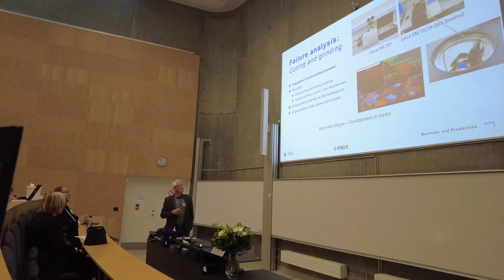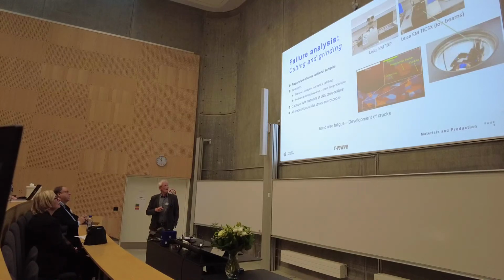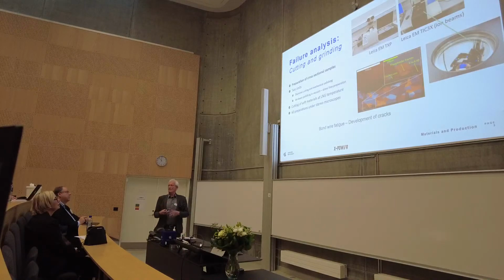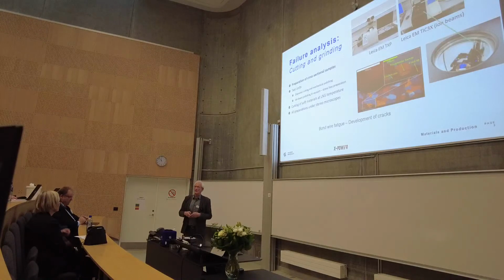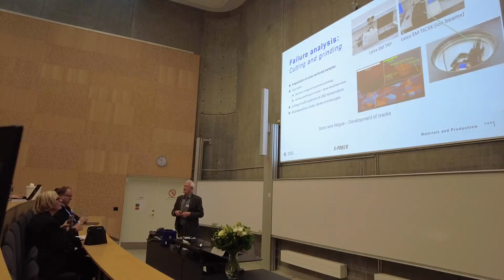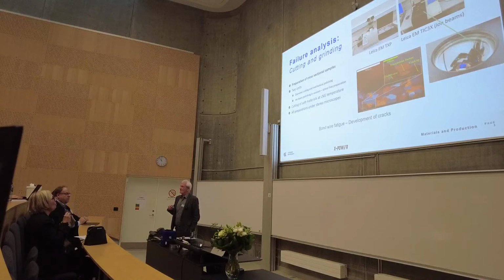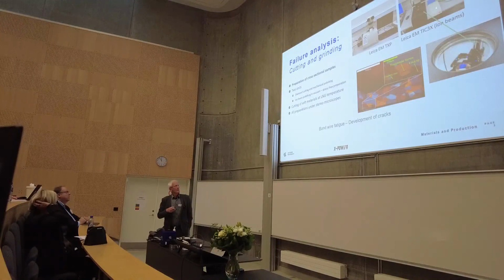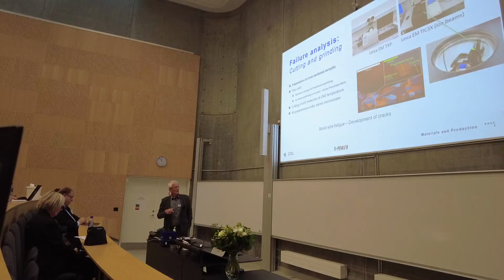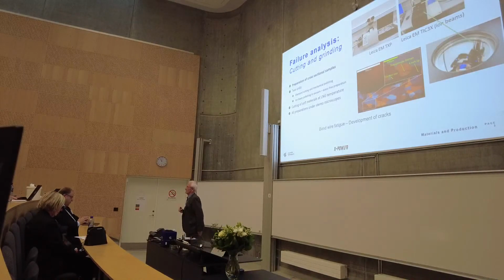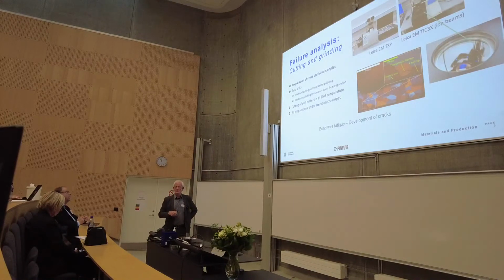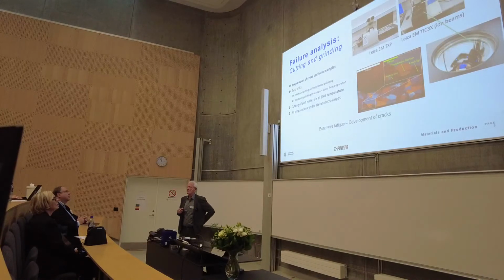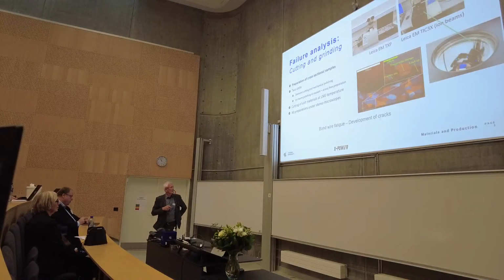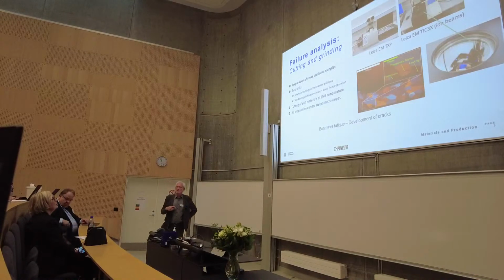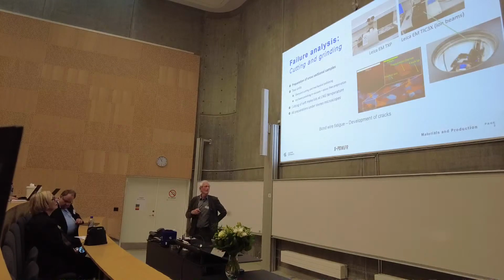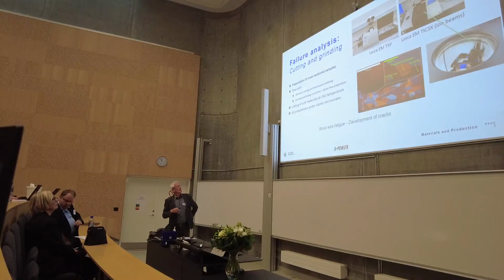This is now becoming somewhat easier because we have a professional system for it. It consists of 2 units from Leica. The first one is where you can cut in with a diamond saw under a microscope and try to isolate the part that you want to look at. Afterwards, in the same machine, you can polish mechanically until you have a smooth surface. But this leaves you with something that's damaged, with strains and so on. So you can move to an ion beam system, which has 3 ion beams. You can see these blue dots there that hit the sample, and so you can sputter away with ions to have a stress-free surface that you can analyze afterwards. Everything is under an optical microscope, so you have nice control of what you're doing. You can cut at low temperature, under liquid nitrogen temperature, which means that you can take polymers, soft materials also, and cut into them. So everything can be under controlled circumstances.